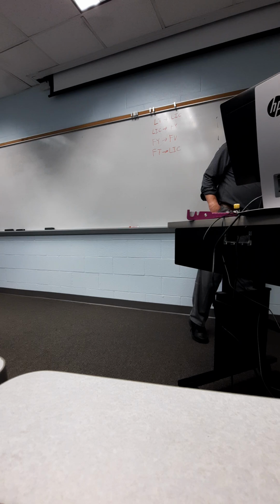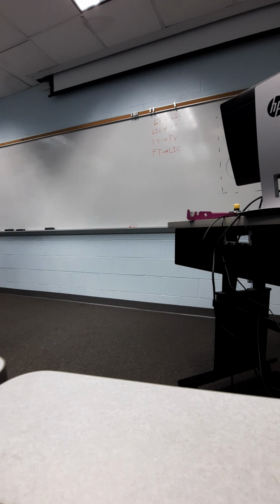Your level loop is the big one. This is the control for it, but this is our process and measured variable going back—it's a bigger loop. So the level loop really contains almost entirely the flow loop. Your big loop is a level loop. That's why the controller is labeled L rather than F, because it's really controlling both F and L. So it's like, which process variable should we list in the tag? Now you know—the main process variable is what gets listed when there are multiple.